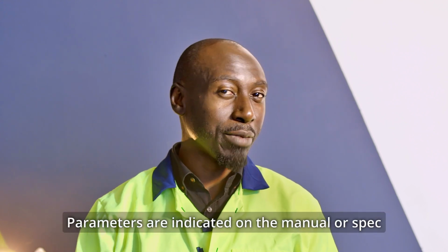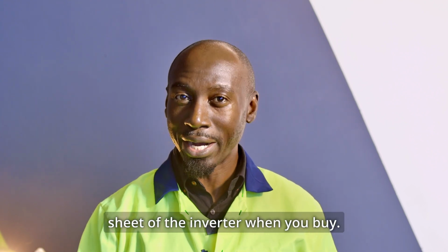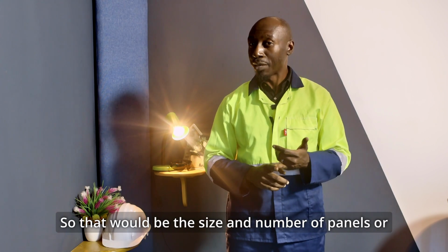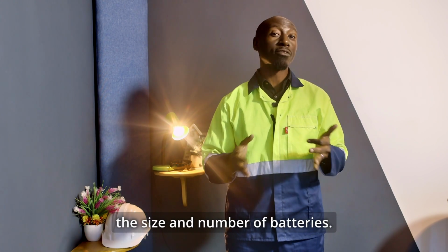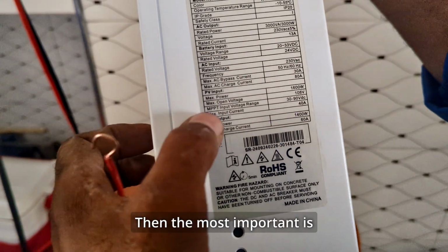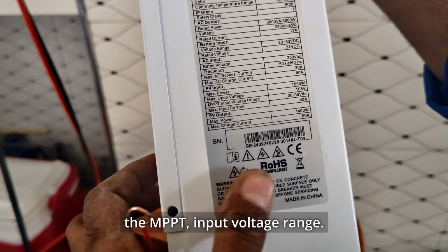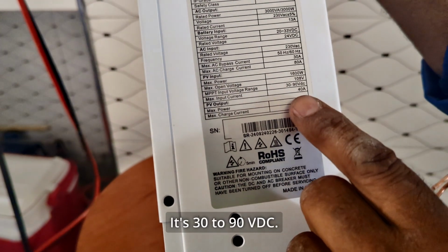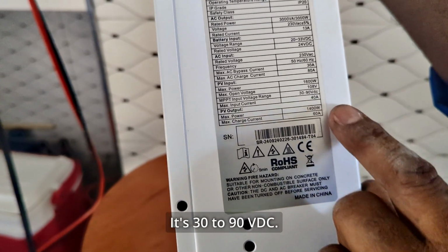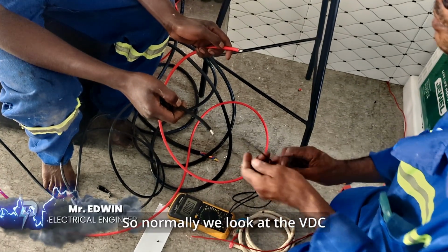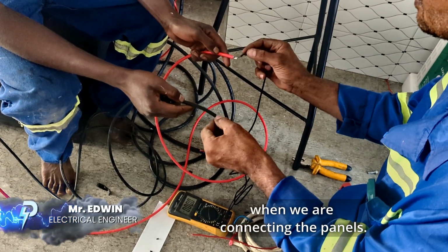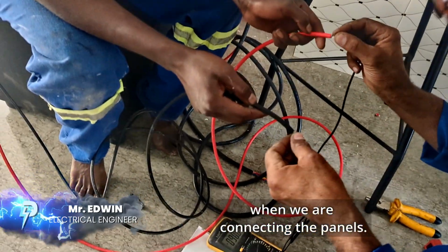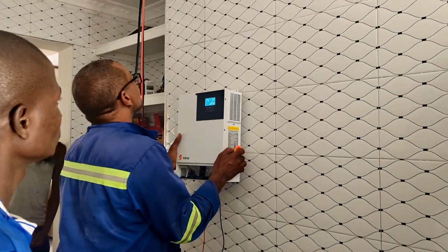Parameters are indicated on the manual or spec sheet of the inverter when you buy it, including the size and number of panels or batteries. Then the most important is the MPPT input voltage range, which is 30 to 90 VDC. So normally we look at the VDC when connecting the panels.